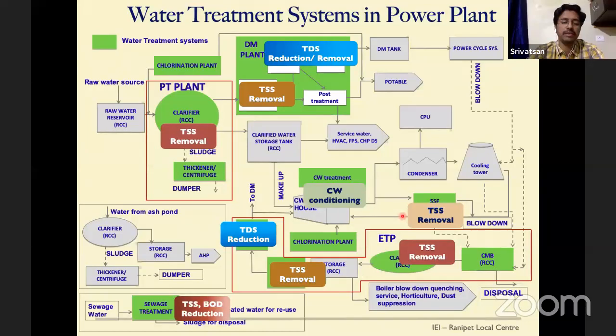Next, we have a sewage treatment plant. The toilets in thermal power plants are interlinked and connected to a common collection pit, wherein we treat this water for sewage, remove the suspended solids, then the biodegradable items, and then reuse it for horticulture or toilet flushing. So basically, whatever treatment we are discussing here in thermal power plants consists only of suspended solids removal or dissolved solids removal. One more thing we have to add is the disinfection system present in thermal power plants.